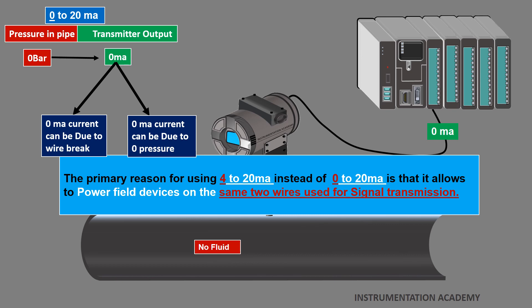While using 4 to 20 mA current signal, since there will be at least 4 mA flowing through the loop, the connected instrument can be powered using the same two wires that transmit signals.